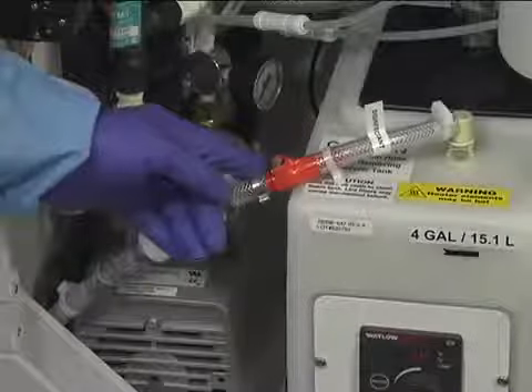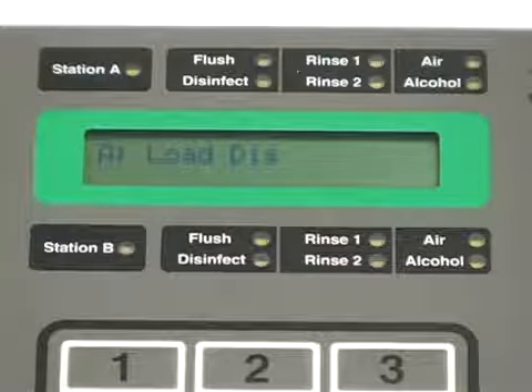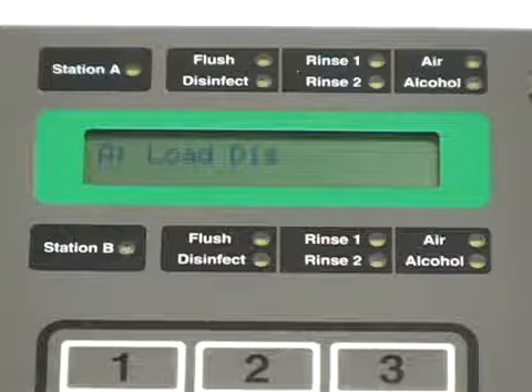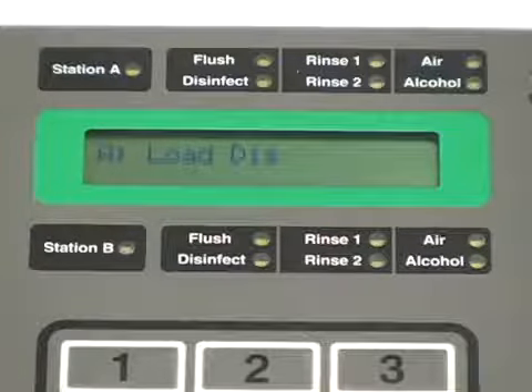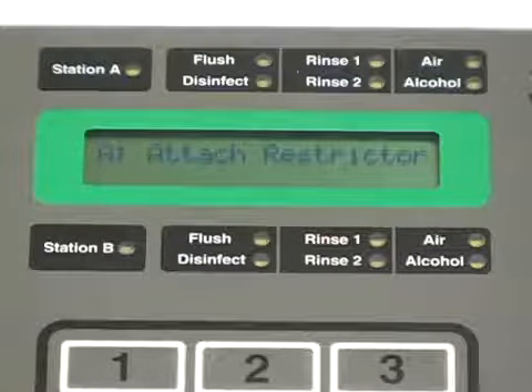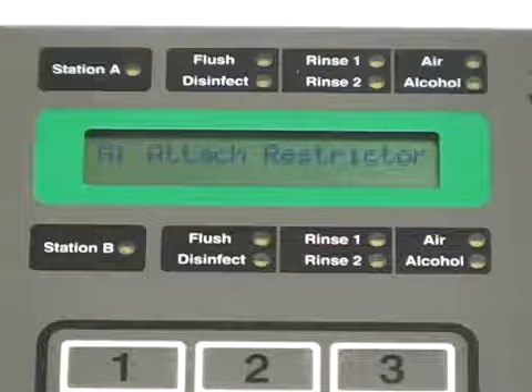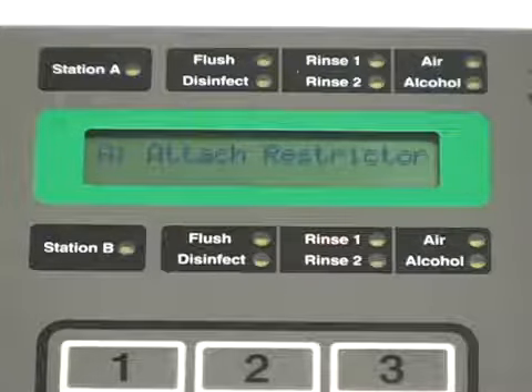First, change the disinfectant filter. Choose the appropriate station on the control panel. Press Setup 1 on the numeric keypad, and then press Enter. On the LCD screen, the letter of the station you are loading with disinfectant will show, followed by Load Dis. Press the Start key. The DSD-201 will prompt the user to attach restrictor.